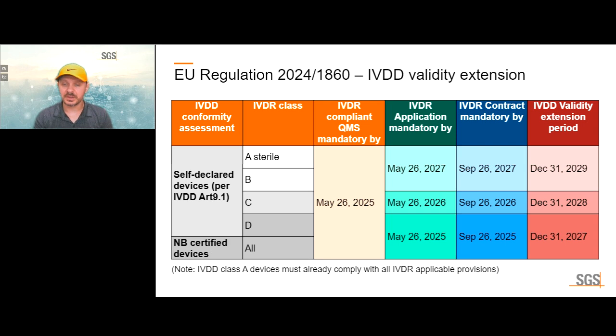Four months after the application, the contract must be signed by the notified body. These are mandatory milestones for manufacturers to keep benefiting from the IVDD validity extension. If they meet the deadlines, they can keep selling their IVDD-compliant product until: end of 2029 for the lowest risk devices, end of 2028 for class C, and end of 2027 for high risk devices. IVDD class A devices must already comply with all IVDR applicable provisions.